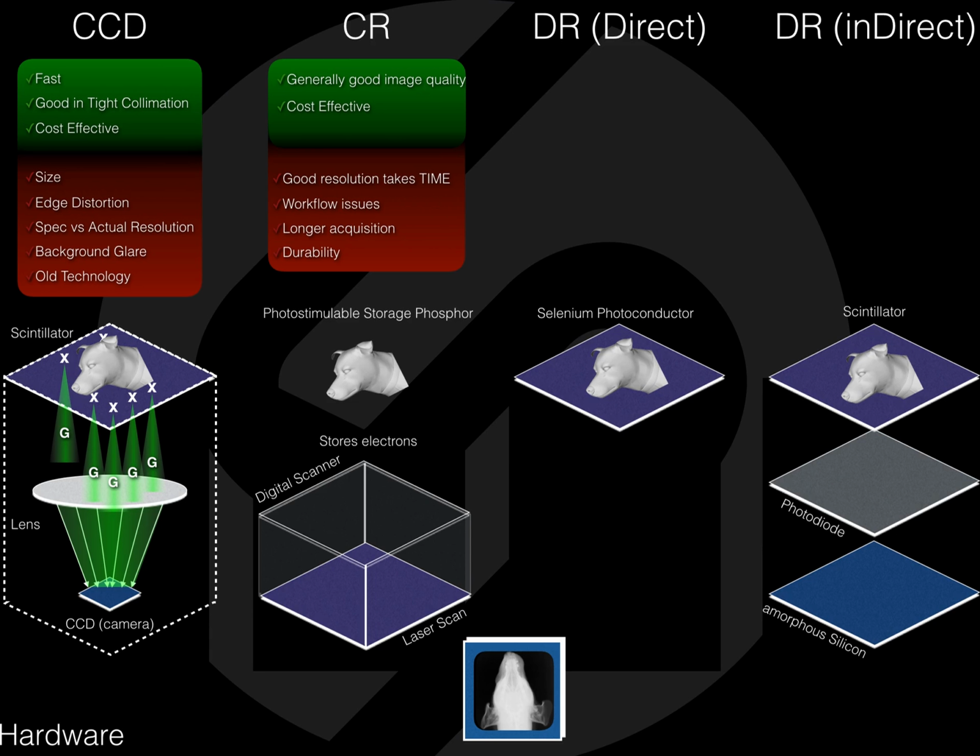radiography staff. Also, the resolution achieved is dependent on the speed of the scanner. The faster the scanner progresses through the cartridge, the more blur appears in the final image. So while current models have increased their acquisition speed, they still fall well behind the digital flat panel detectors to follow. The principal manufacturers of CR systems that are still available in the veterinary space are Agfa, Fuji, FireCR, ScanX, and Konica Minolta, with an average price between $10,000 and $20,000.